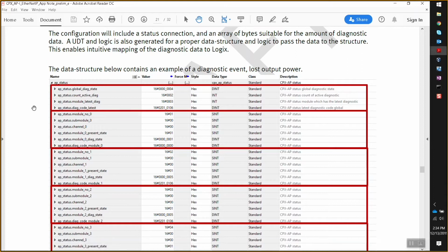If you're able to create an error now, one of the easiest errors to create is to remove the pin for the load power, not the PS but the PL. I don't know if you're able to switch that off easily. If not, you could disconnect the AP connection between module 1 and module 2, and there you'll trigger an error also. I'm going to disconnect the communication cable to the manifold, which is the last module.